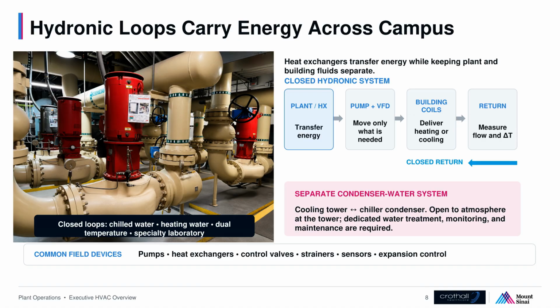Plant capacity reaches the buildings through hydronic loops. Most of the chilled water, heating water, dual temperature, and specialty laboratory systems are closed loops. Heat exchangers transfer energy between the plant and building sides while keeping the fluids separate. Pumps, often controlled by VFDs, move the water. Control valves regulate coil capacity, and return temperature and flow tell us how much useful energy was delivered.